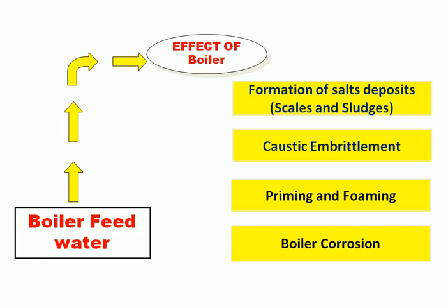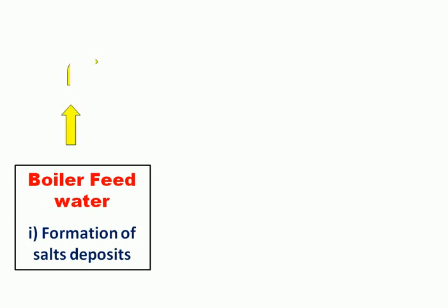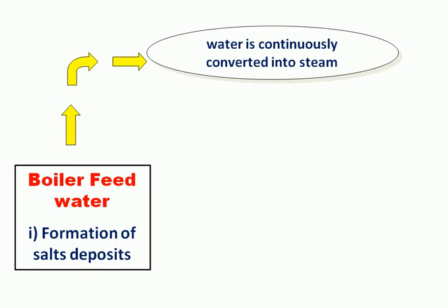In case water contains hardness, turbidity, oil and grease, impurities, and dissolved salt, these four types of disadvantages occur. We are discussing them one by one. First, formation of salt deposit. When boiler feed water contains hardness and dissolved salt impurity, as water is continuously converted into water vapor (steam), the dissolved salts in soluble form reach the saturation point and get deposited as salt deposits.